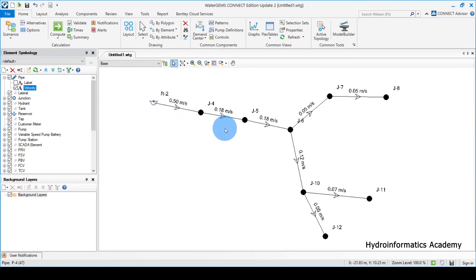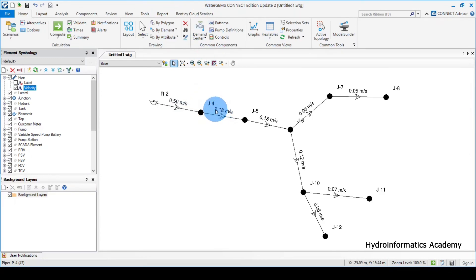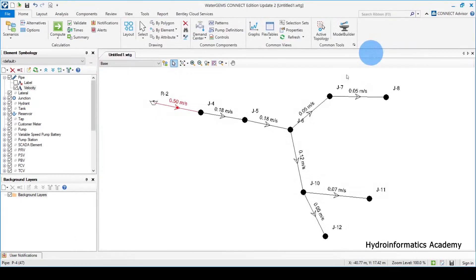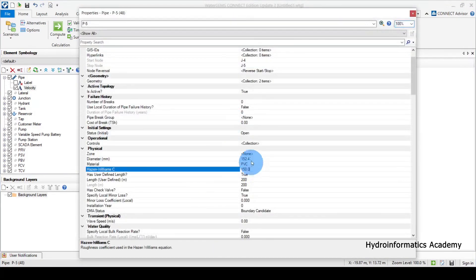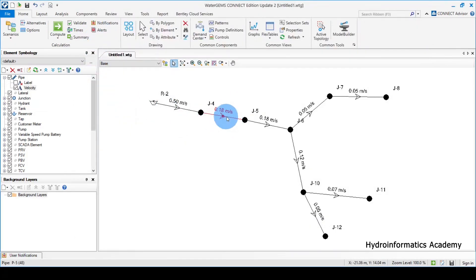Now I'll continue optimizing the model. When optimizing, always start from the first pipe — the one connected to the source. The first pipe is done at 0.5 meters per second. The next pipe still has 0.18, so I'll adapt the same diameter value of 90mm for that pipe as well, going from 152 down to 90. Let me click Run and see if the value changes.